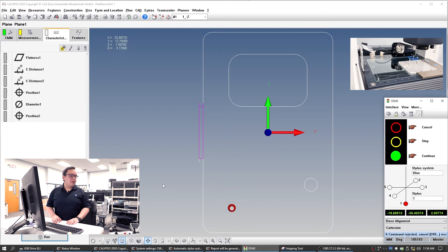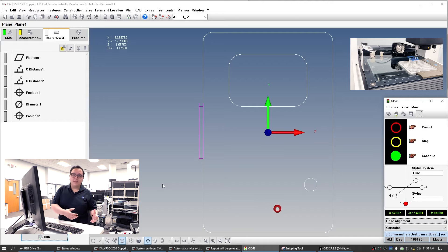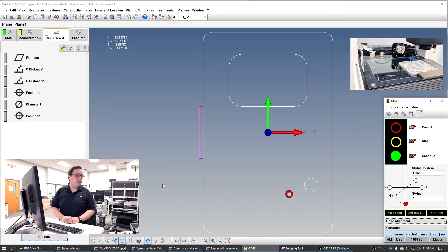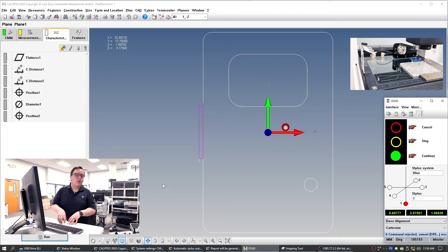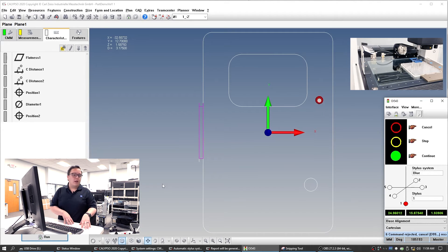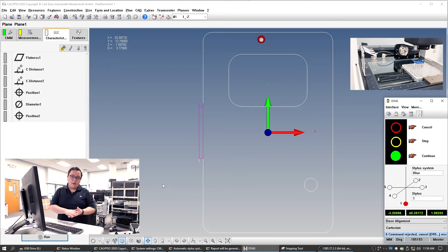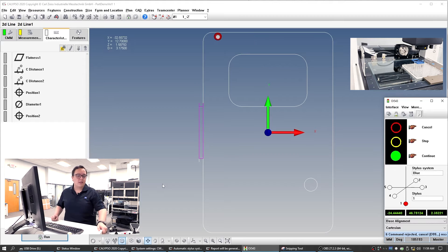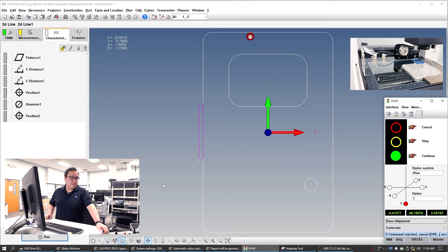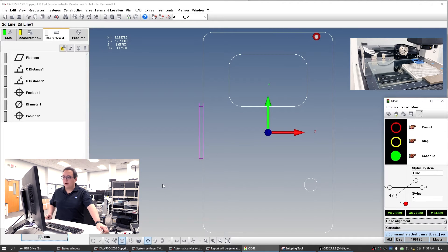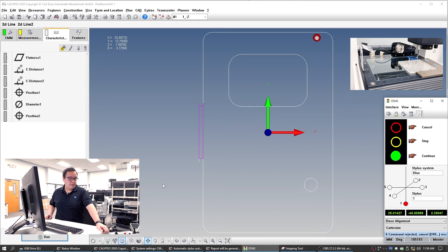Once you're debugging the program, something you'll start to take note of is: okay, this is a big plane — we can actually go a little faster. So instead of the 7.5, we could have done maybe 10 or 12.5. You'll get a sense for these things the more you use them. Now if it was a really tight tolerance, I would always recommend going slow — the tighter the tolerance, you want to make sure that you really get those points. Because at some point we're just chasing microns, and we want to make sure they're correctly measured and correctly reported.